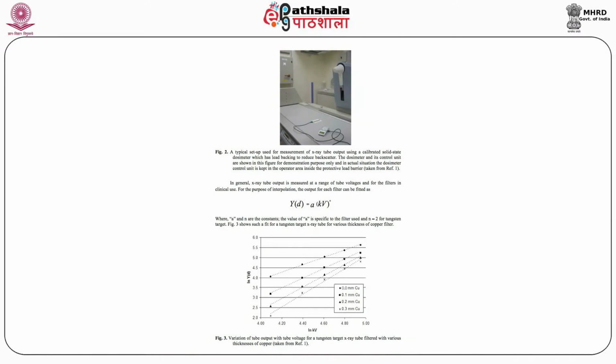The tube voltage in fluoroscopy, computed tomography and general radiography covers the range of 50 to 150 kV, the anode material usually being tungsten. Mammographic examinations are conducted with tube voltage between 22 kV and 40 kV, and various combinations of anode and filtration materials are used. The most common materials are molybdenum anode and molybdenum filtration.